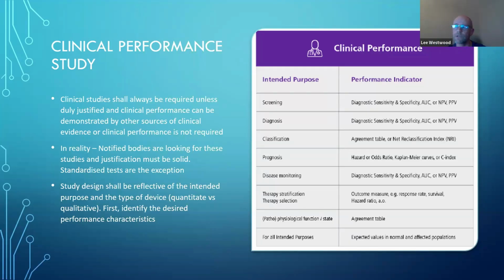But the first thing you want to do is identify what the performance characteristics of your device are going to be. So what your study endpoints are going to be. So from your intended purpose, say you've got a screening device, a typical IVDR defined clinical performance characteristic would be diagnostic sensitivity and specificity, or positive predictive value or negative predictive value. But the flip side of that, in order to have diagnostic sensitivity and specificity, you've got to have cutoffs. Cutoffs demonstrated analytically. So cutoffs are like medical decision points, which is very difficult to do.